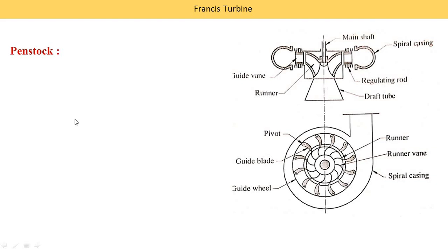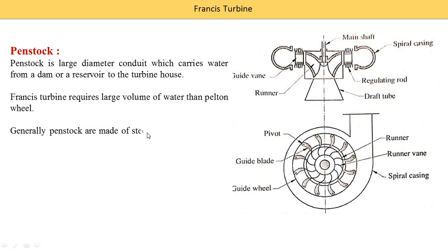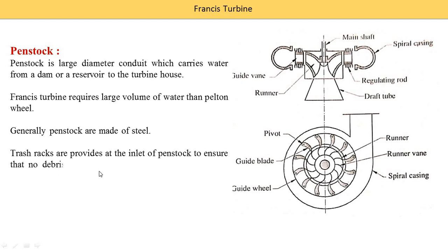First is the penstock. Penstock is a large diameter conduit which carries water from a dam or reservoir to the turbine house, supplying water up to the turbine inlet. Francis turbines require a larger volume of water than Pelton turbines. Penstocks are made of steel or concrete depending on the quantity of water and available head. Trash racks are provided at the inlet to ensure no debris or foreign matter enters the penstock.